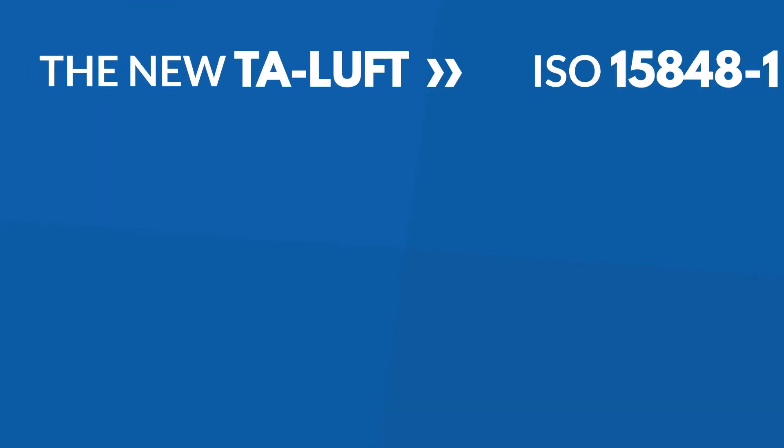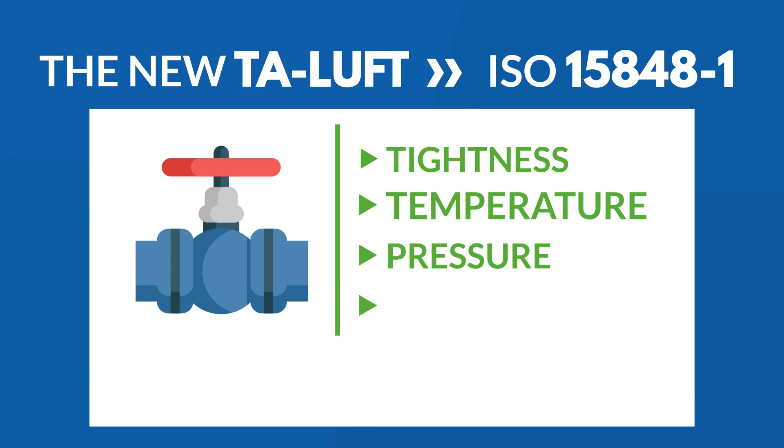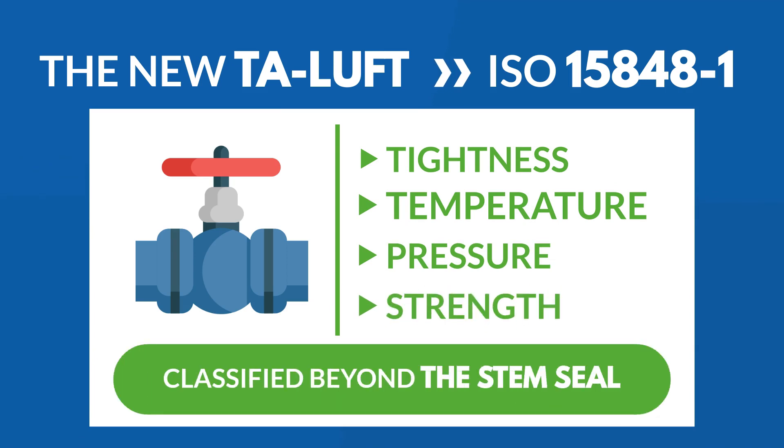The situation is different with the TA Luft amendment in accordance with ISO 15848-1. First, the tested valves can be categorized using performance classes according to leading parameters such as tightness, temperature, pressure, and strength, meaning the entire valve is classified beyond the stem seal.